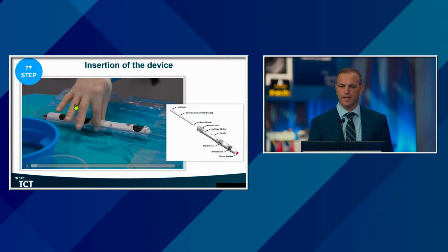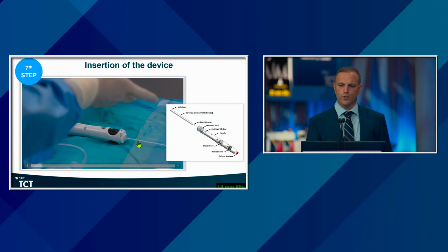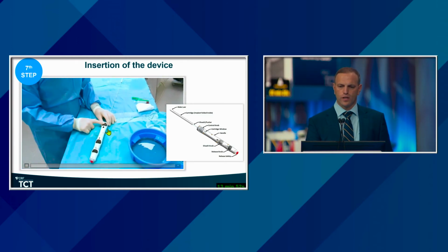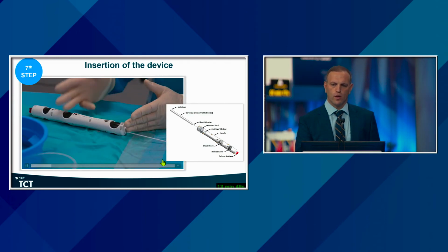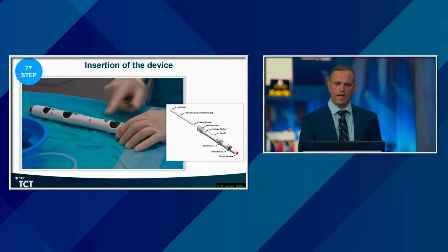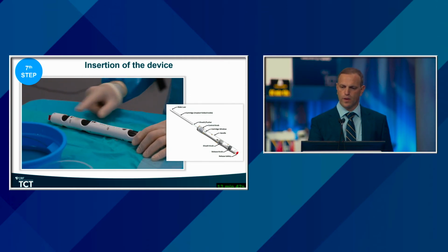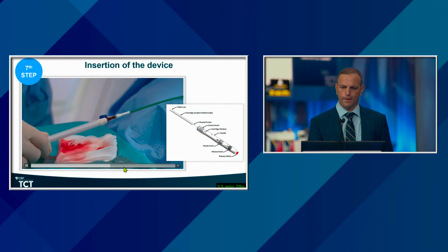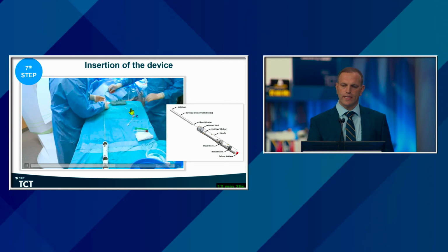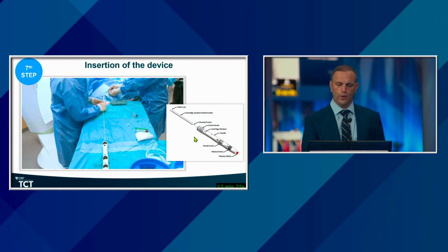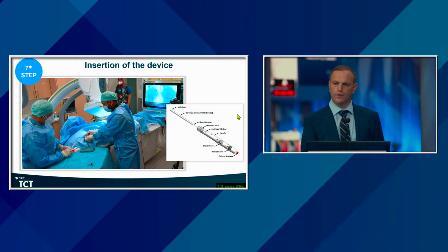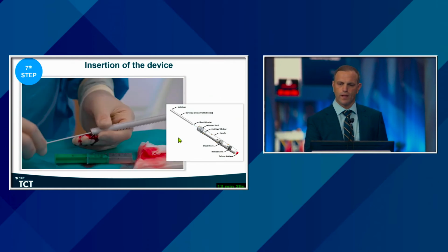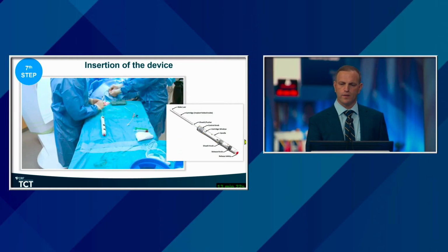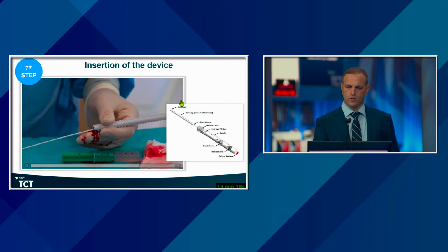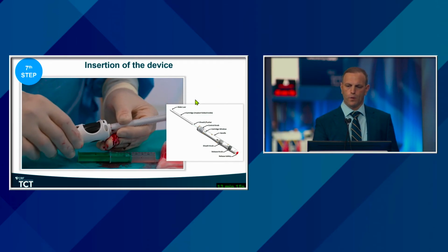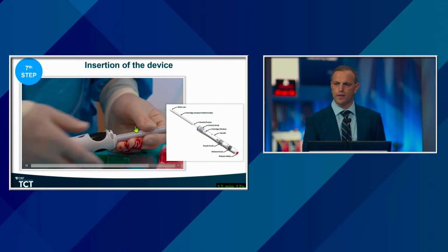Unpacking of the device, this is the handle, and it's easy to use because you don't have much. We have only 3 knobs. First one, second one, third one. First one with a black and a white arrow direction, and the other ones with the black arrow direction. Connected with the delivery catheter, it's Luer lock, and then we are going through with the device into the delivery catheter. First step slowly, and then it's easy, and we connect the handle here by turning the first knob in black arrow direction.